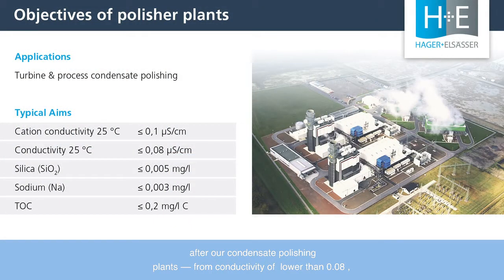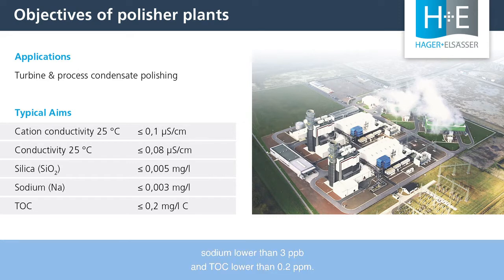What values would you expect? We would expect the following values on the clean condensate after our condensate polishing plants: conductivity lower than 0.08 micro siemens per centimeter, silica lower than 5 ppb, and sodium lower than 3 ppb.